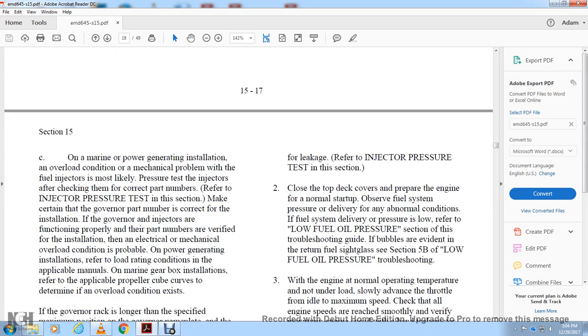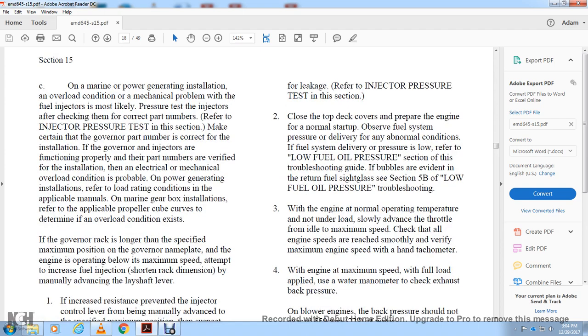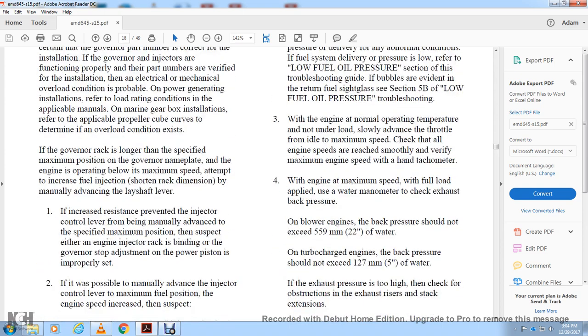On marine, power generator, and stationary installations, an overload condition or mechanical problem with fuel injectors is most likely, perform an injector pressure test and check for correct part numbers. Make certain all governor parts are correctly numbered and that the governor is functioning properly. Verify the part number for the installation and check whether an electrical or mechanical overload condition is probable. On power generating installations, refer to load ratings in the applicable manuals. On marine gearbox installations, refer to the applicable power curve tables to determine if an overload condition exists.